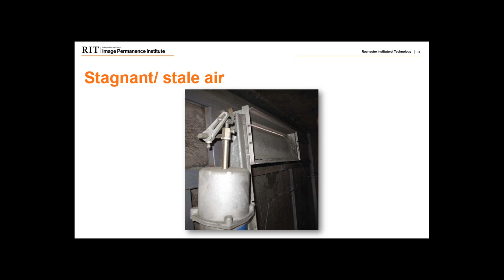So in addition to dampers that are related to the airflow being closed or closed from their full position or intended position, as Chris mentioned, there can also be fire dampers. These are put in place in case of an emergency so that they can drop closed and prevent any smoke and soot from circulating throughout the building. Sometimes these will fall closed over time, or something might trigger them that you may not be aware of. And so as long as these remain closed, again, airflow is not getting to the space. So if you hear complaints about this, it might be a good indicator to look at some of those dampers. All right, I'm going to wrap up here with a few examples of some operational issues that we see.